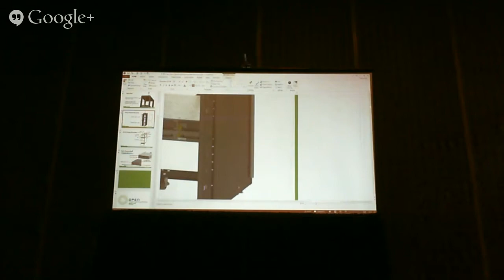And then there's also a third piece, back here in the back. That piece provides structural support for the bus bar cage that's running along the entire length of the rack. Even though the bus bars themselves are broken into two separate zones by location, the cover piece that protects the bus bars, as well as the people using the gear from the bus bars, is one continuous piece that goes from the top to the bottom. So that third piece behind the bus bar cage provides some horizontal stability to make sure it's in the right spot.